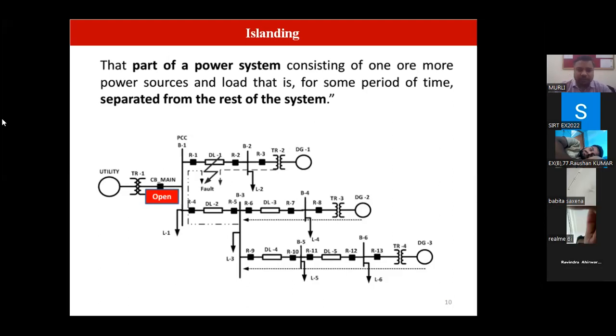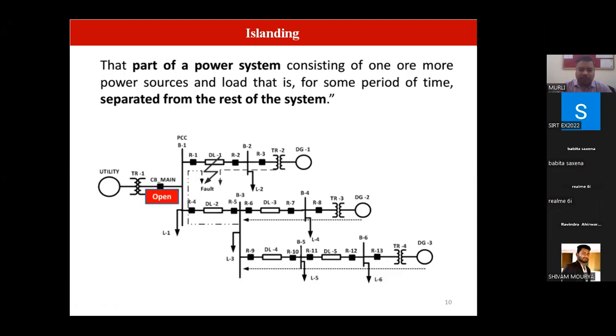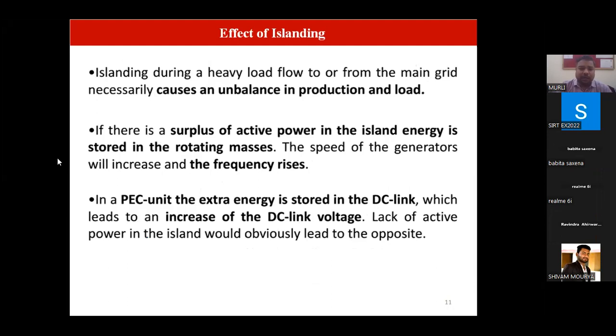Okay. So, as far as we talk of the islanding scenario, if this circuit breaker switch is open, then we can say that there is no interconnection between the utility grid and the microgrid, and that scenario is called the islanded system. A power system consisting of power sources that can be separated from the rest of the system is islanding. So what is the effect of islanding, and why do we need to detect it?